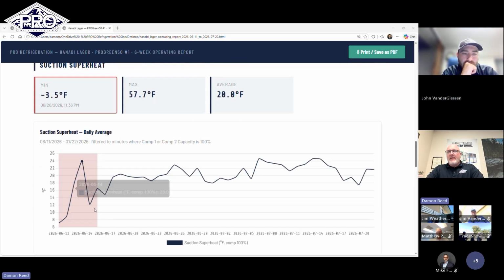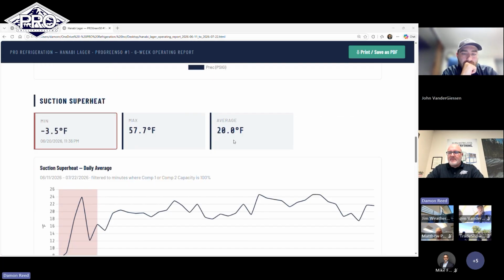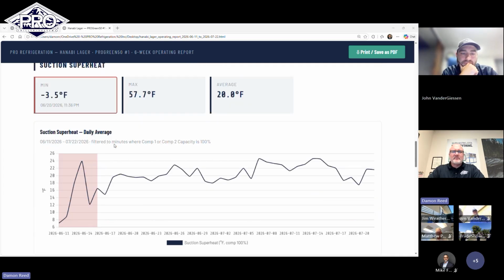Down into the remainder of the time, we're averaging 20 degrees of suction superheat. That's a beautiful suction superheat range. 57 as the max. Those are some of the highs that we pick up when we do a start-stop of a compressor. And so I kind of disregard those when we look at those a little deeper.